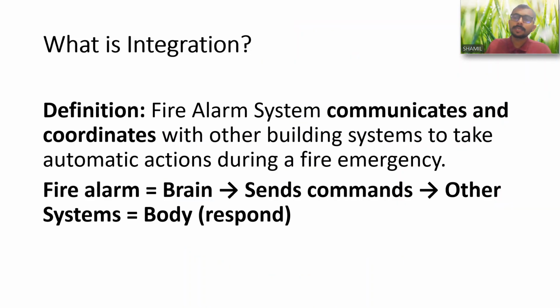Integration is the communication of the fire alarm system with the other systems installed in the building in order to provide an automated response during an emergency situation. So if a fire alarm activates, the associated systems in the building, for example BMS, HVAC, public address, elevators, sprinkler systems, etc., how they are automated, what commands and actions these systems need to take in order to provide a safe evacuation for the occupants. This is what integration is all about.